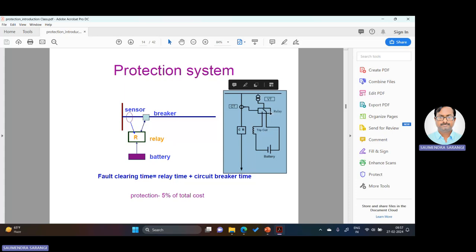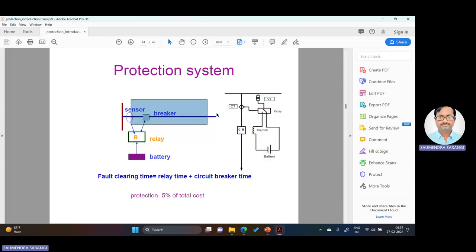Normally, we have an operating limit for our transmission system, and this operating limit is designed. Suppose for voltage, a 10% variation is acceptable. For the current, 20% higher may be allowed. Suppose 100 ampere is the load current, up to 120 ampere can be tolerated. However, during the fault the current will be 7 times higher, 700 ampere or something like that. So that will burn the circuit.